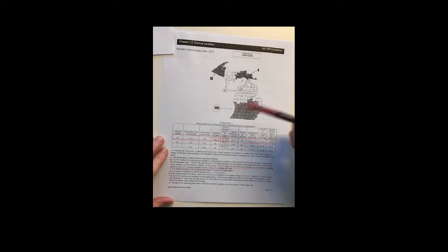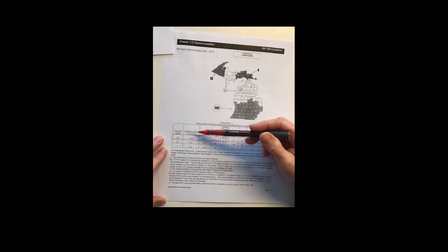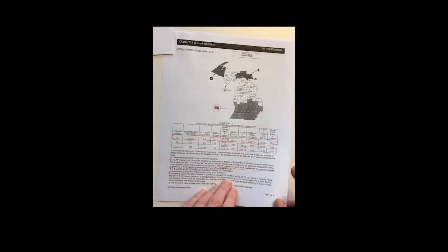Remember, it's often given to you as a U value for that piece of it. And if you look at the Michigan Energy Code, it even gives the factors for fenestration as a U value because that is typical. You need to convert that to an R value by taking the reciprocal of that number.